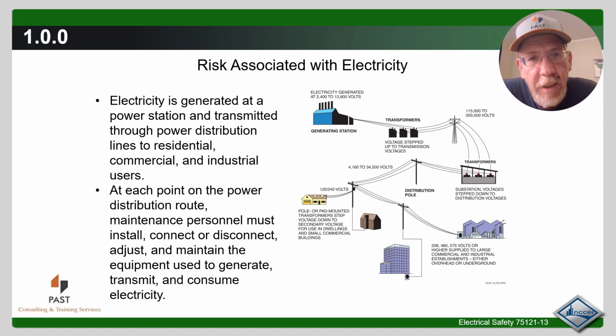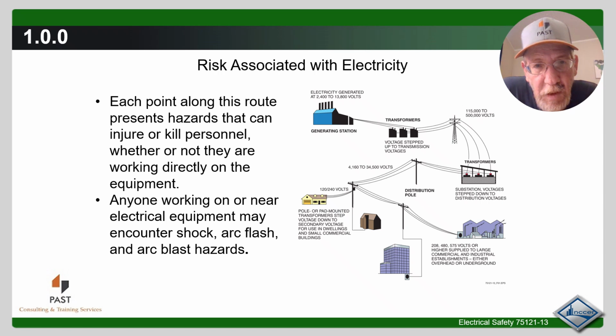Electricity is generated at a power station and transmitted through power distribution lines to residential, commercial, and industrial users. At each point on the power distribution route, maintenance personnel must install, connect or disconnect, adjust, and maintain the equipment used to generate, transmit, and consume electricity. Each point along this route represents hazards that can injure or kill personnel, whether they are working directly on the equipment or not. Anyone working on or near electrical equipment may encounter shock, arc flash, or arc blast hazards.